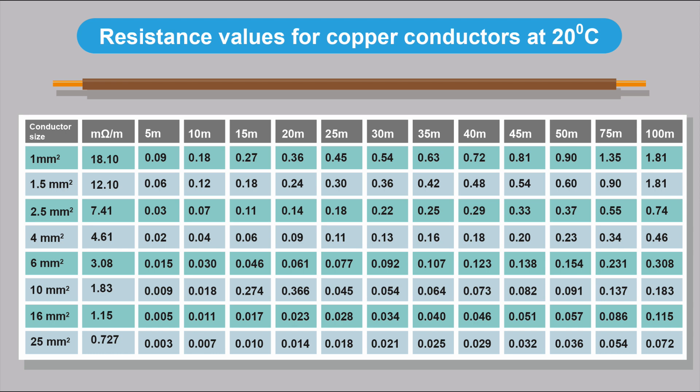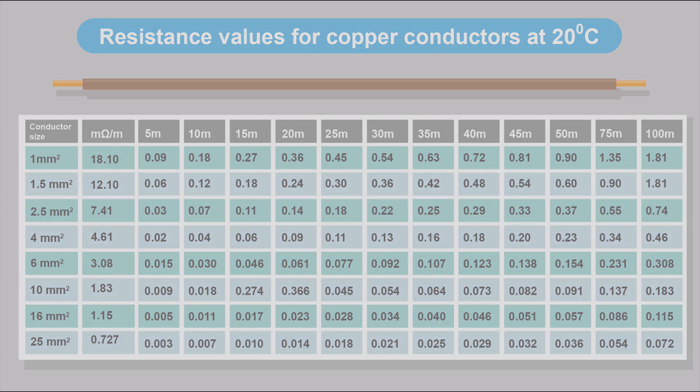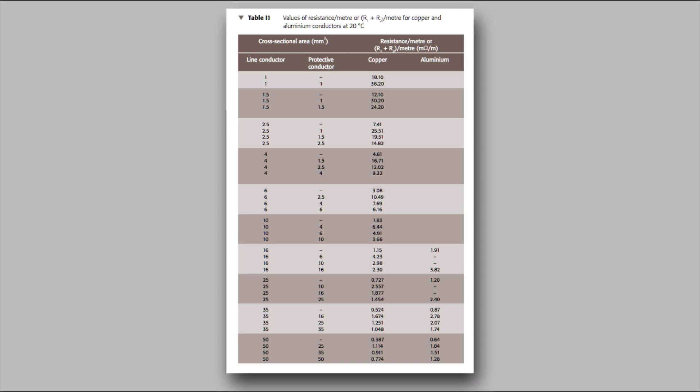So if you've got 35 metres of 6mm cable, you should be expecting a reading of 0.107 ohms. If you've got 50 metres of 16mm, you'll be getting a reading of 0.057 ohms. And you can find all these values in Appendix I in the on-site guide.